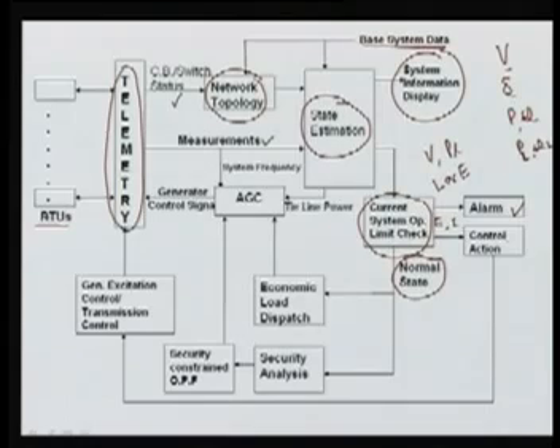Now, if your system is in the normal state, then we can perform the security analysis, and we can also perform the economic load dispatch. Then this information, the economic dispatch, will be passed to the automatic generation control of the power system. Basically, with the AGC we control the output of generators. For AGC, we require various information. First is the system frequency, which is measured from the system through RTUs, and we also require the tie line power flows, because our system may be connected with other neighboring systems.